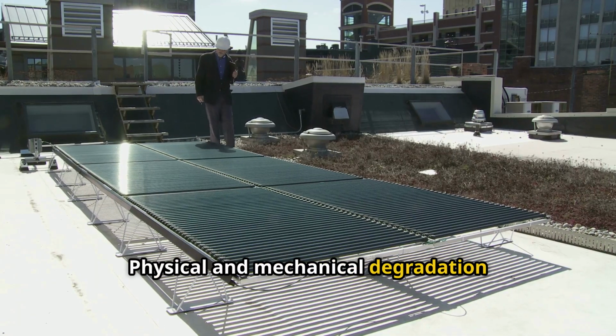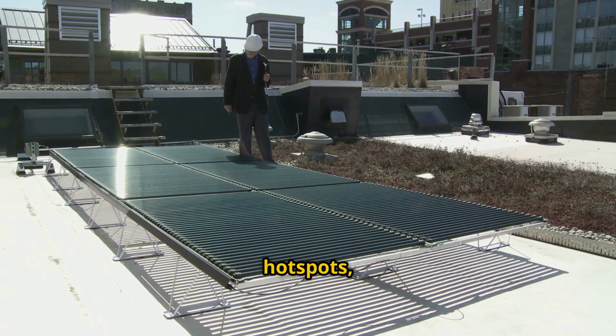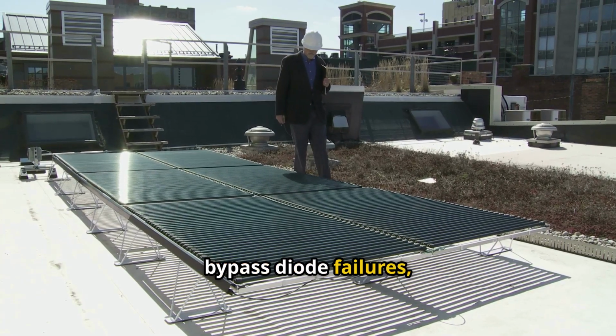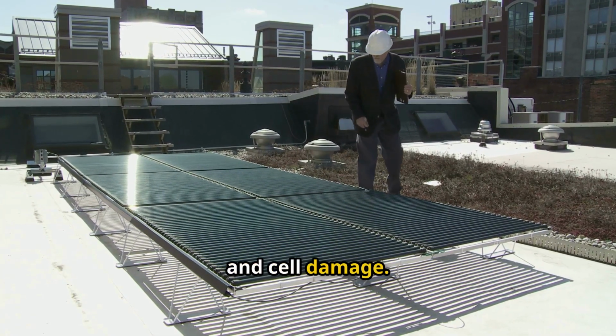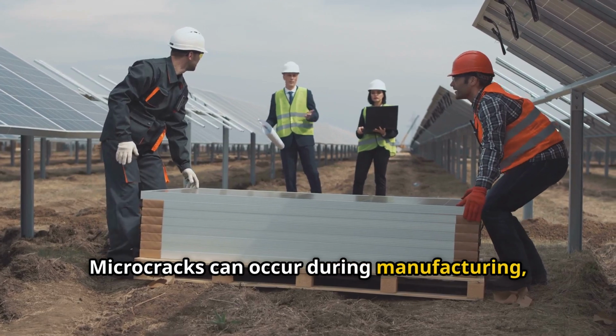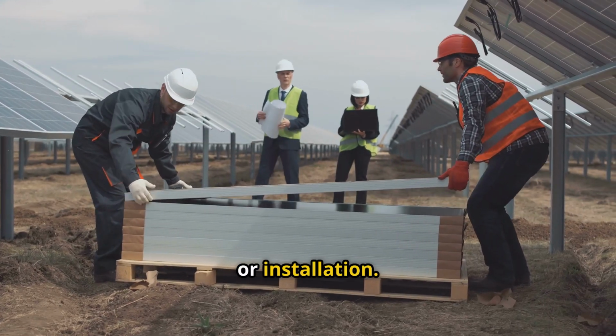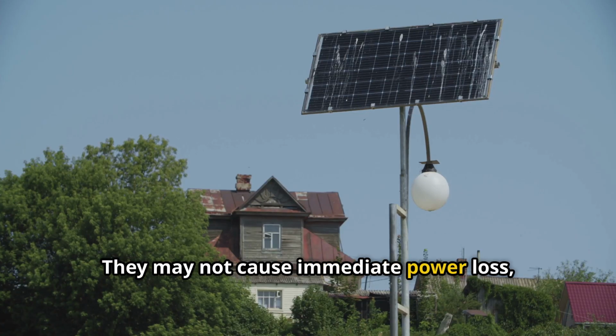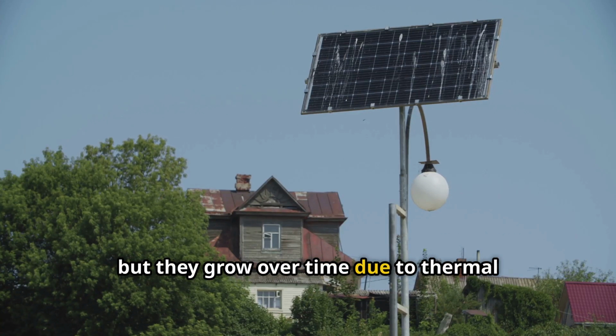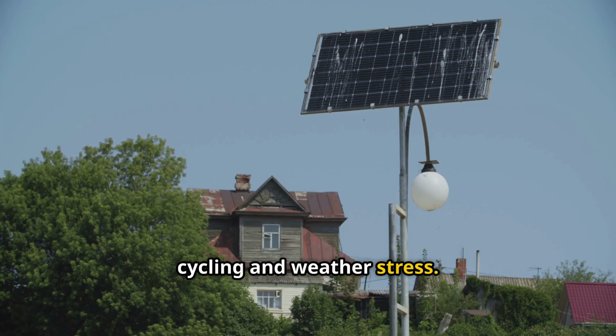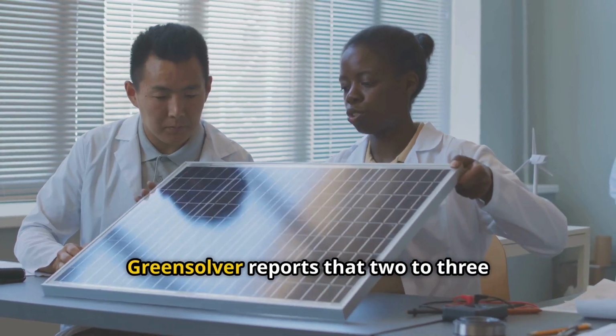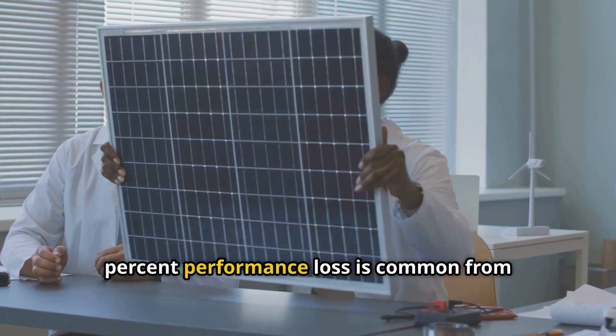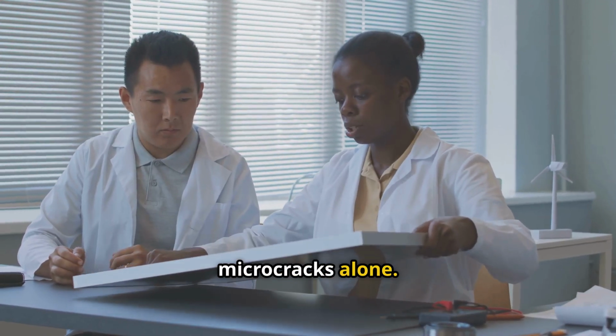Physical and mechanical degradation includes microcracks, hotspots, bypass diode failures, and cell damage. Microcracks can occur during manufacturing, shipping, or installation. They may not cause immediate power loss, but they grow over time due to thermal cycling and weather stress. GreenSolver reports that 2 to 3% performance loss is common from microcracks alone.